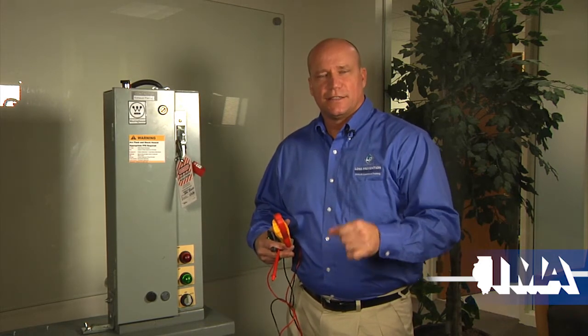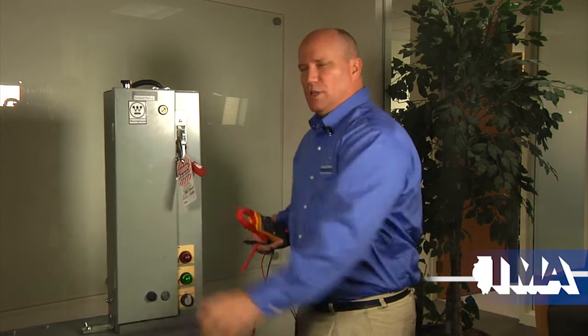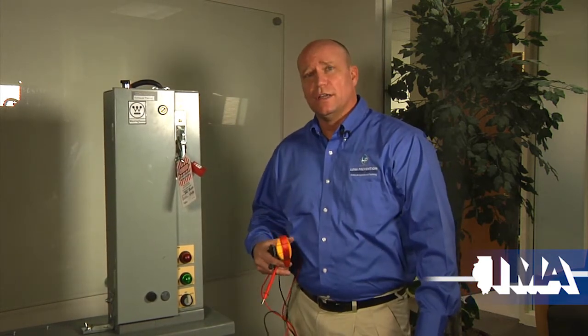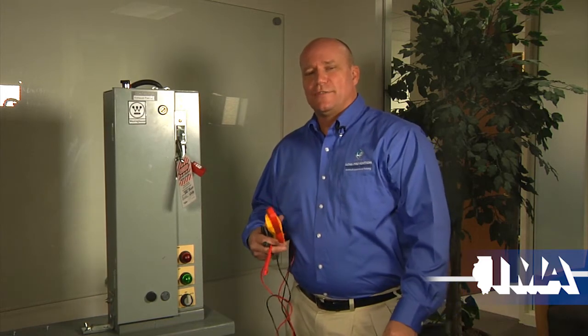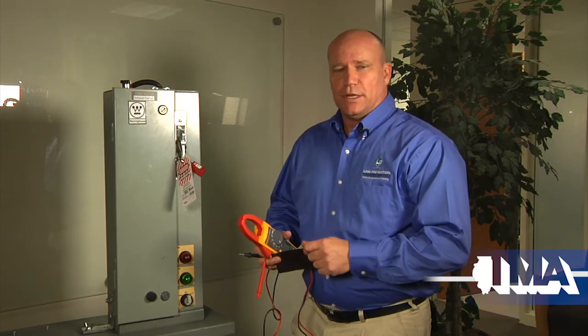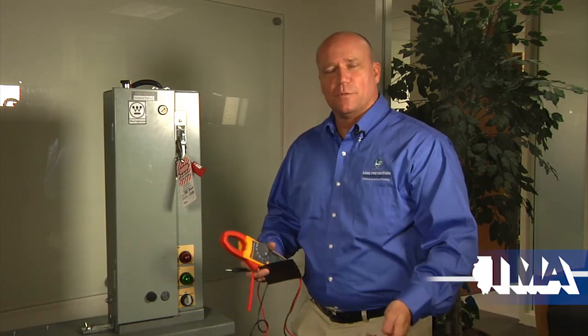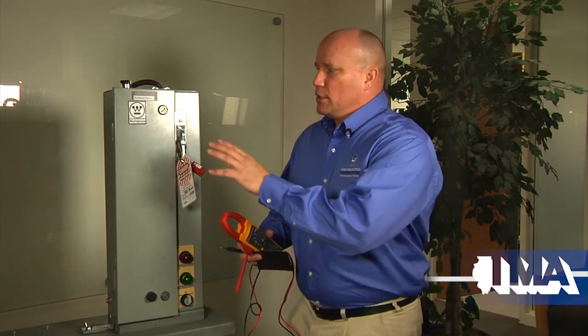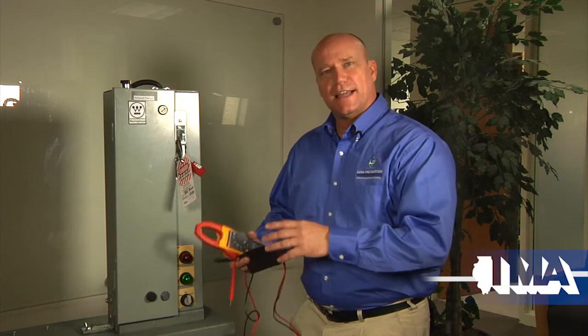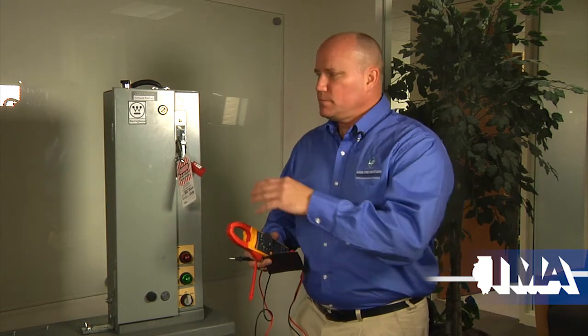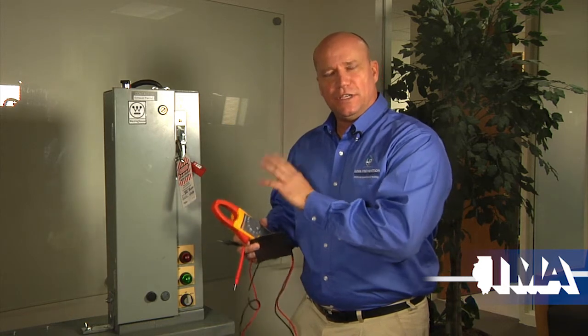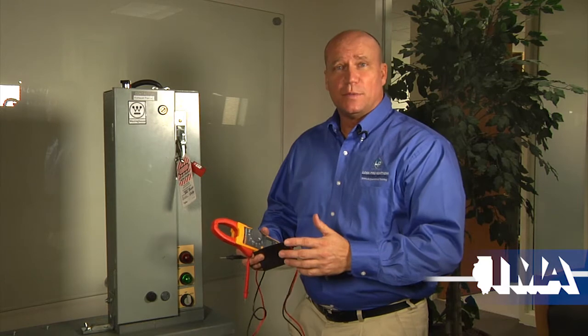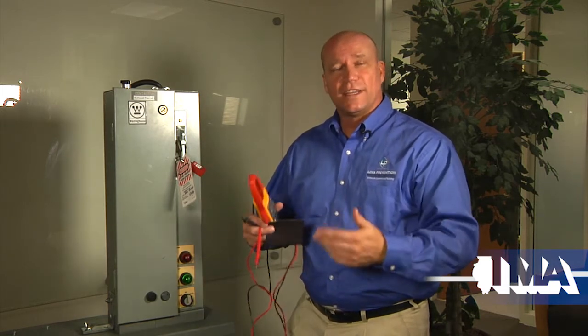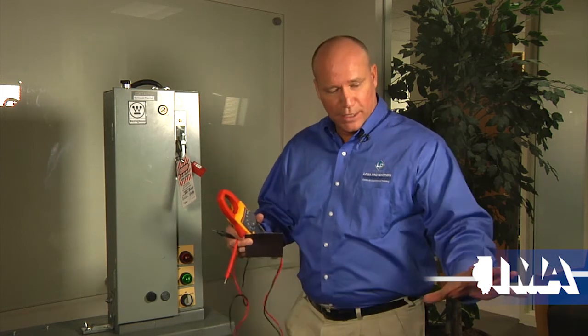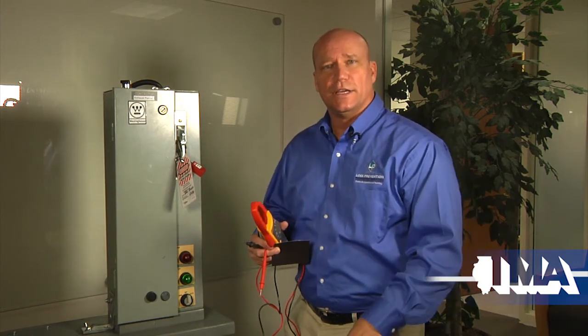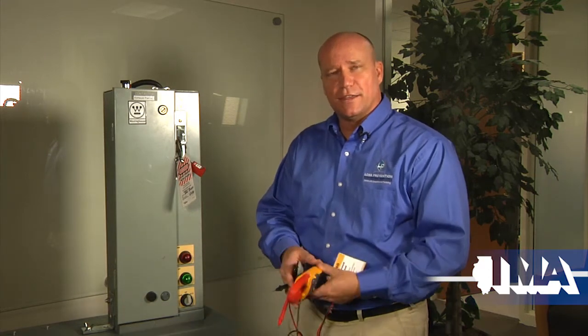The other aspect to that is when you don't have an arc flash label, and it doesn't tell you exactly what to wear and where to set your boundaries. So you have to go to NFPA 70E and look at their tables. Now I don't have a copy of those tables because it's proprietary information, but those tables basically refer you to the type of task you're doing, and then you analyze it based on that task and then several parameters: if what you're doing is unsafe, and if you need to utilize personal protective equipment. And then it refers to another table that, based on that, you determine what category of personal protective equipment you need to wear, and it'll tell you specifically what's part of that category. So that's the NFPA 70E table. So that's the other method that would be available to you.